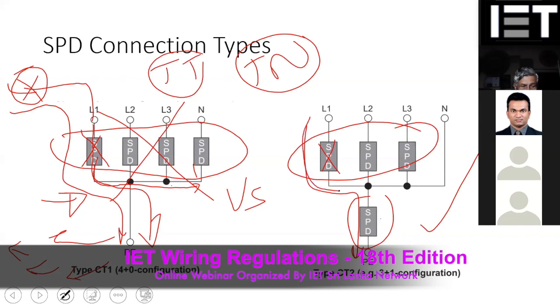Because of that, what will happen? That will be detected as a short circuit, because there is no SPD in the neutral connection. Here the problem is you have an SPD in the neutral connection, so it's like an open circuit. But here it is already connected, with no SPD, so if there is a short or leakage in the SPD, that will be detected as a short circuit, and the upstream protective device will detect it and cut off the circuit. You will not get a sustained earth fault situation if you connect it like that. That's why we are recommending this arrangement for TT.